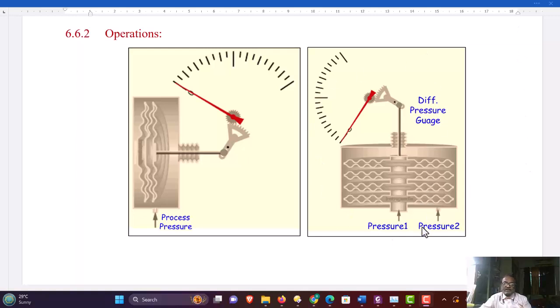Here in another figure, a differential pressure gauge is shown. In the first figure, the pressure is measured with absolute reference, whereas in the second figure, differential pressure measurement is done. The reference pressure is allowed to go inside the capsule via pressure port 2. Normally, the reference pressure in a differential pressure gauge is atmospheric pressure. So this port is open to the atmosphere, and the measurement port is connected to the external pressure fluid. It can be gas also.